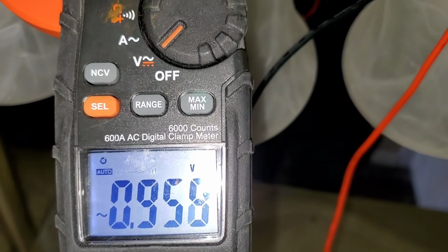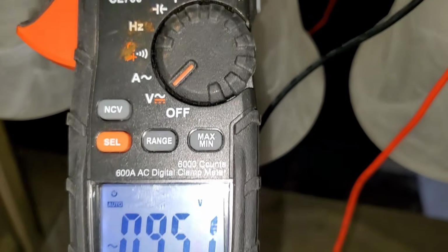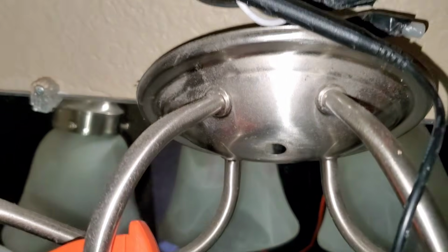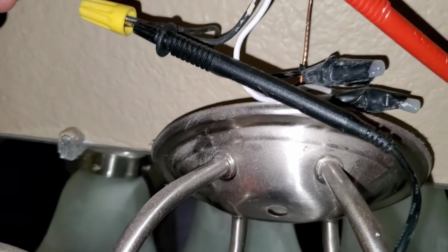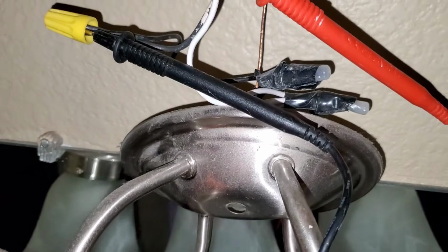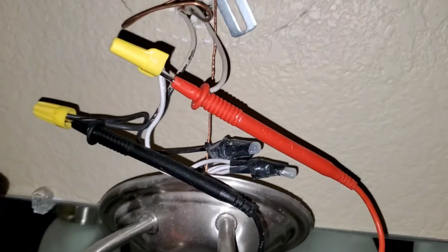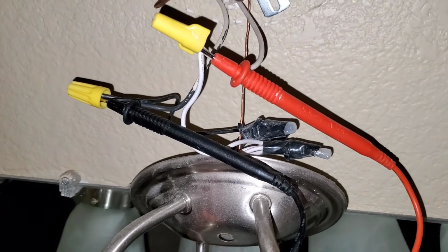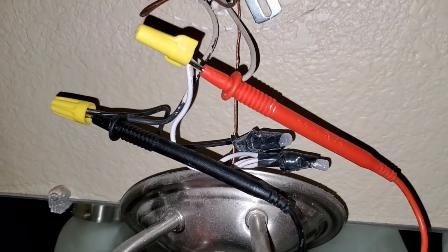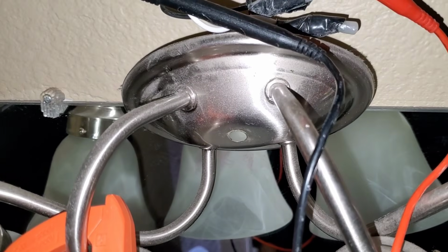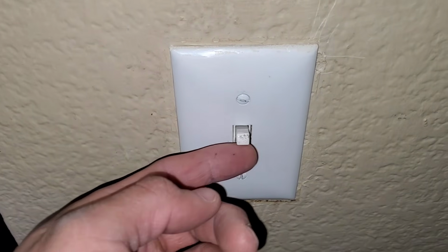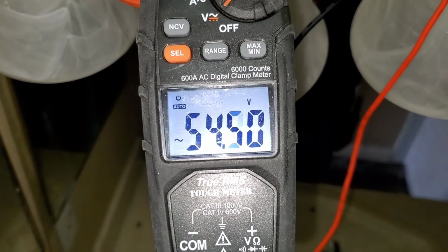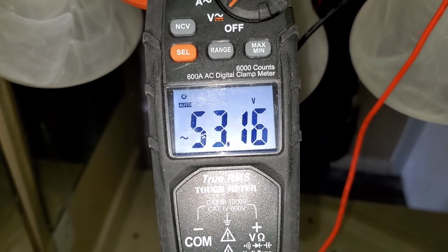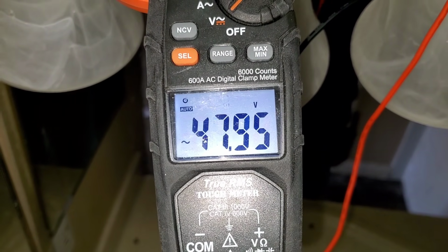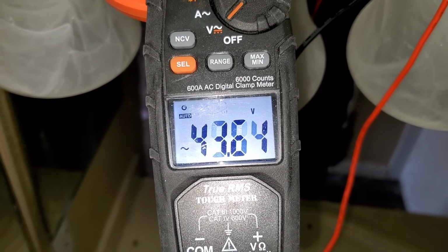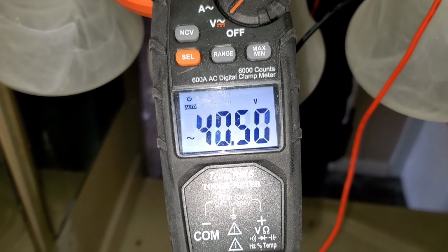So here I have my multimeter set to volts AC, and I did remove the wires with the wire nuts and shove each of my leads going into the wire nuts. And what I'm going to do is turn the light switch on and see if I have 120 volts feeding my light fixture. Now I'm going to turn the light switch on. And here I'm only getting 54 volts. So this indicates to me that I'm not getting the 120 volts coming in from my light switch.